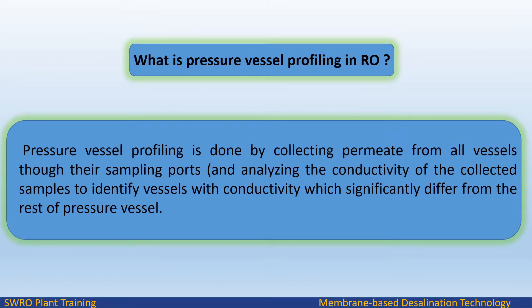What is pressure vessel profiling in RO? Pressure vessel profiling is done by collecting permeate from all vessels through their sampling ports and analyzing the conductivity of the collected samples to identify vessels with conductivity that significantly differs from the rest of the pressure vessels.